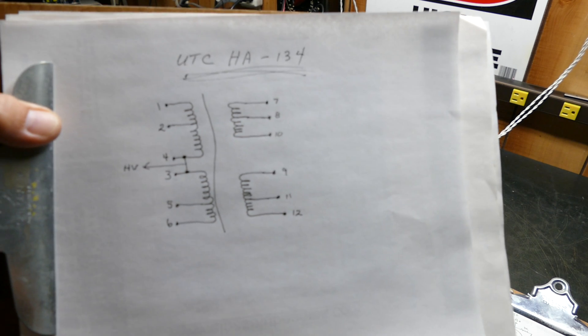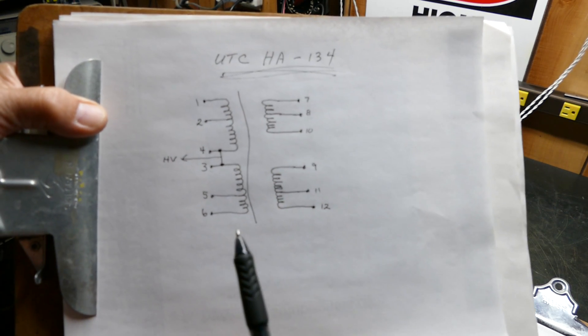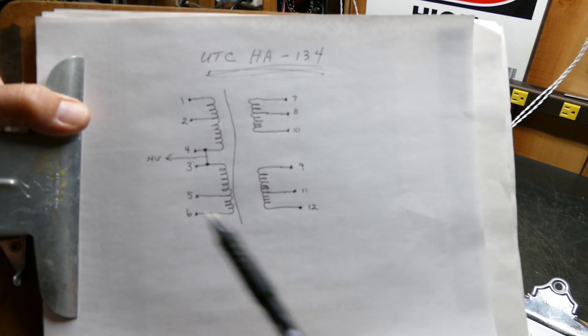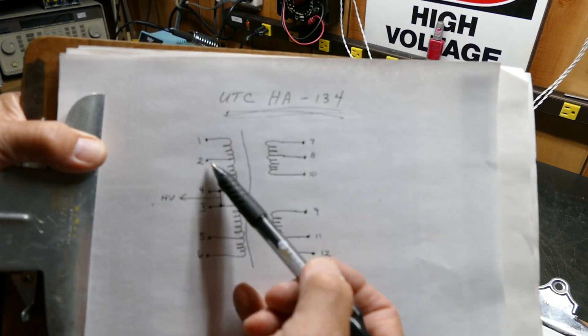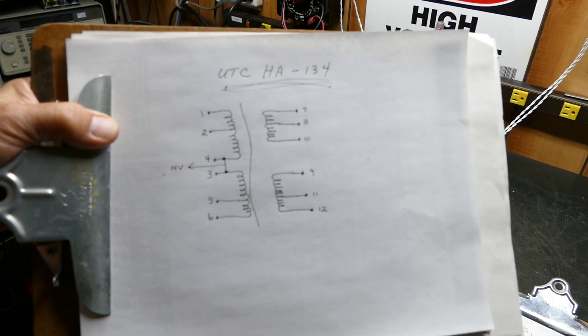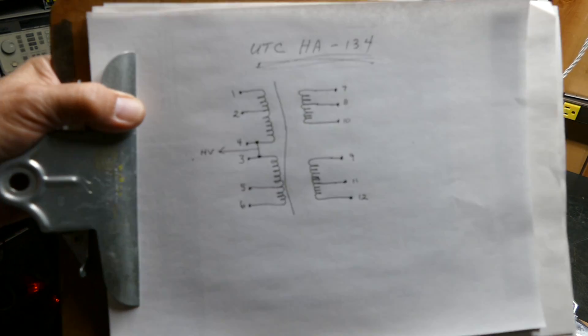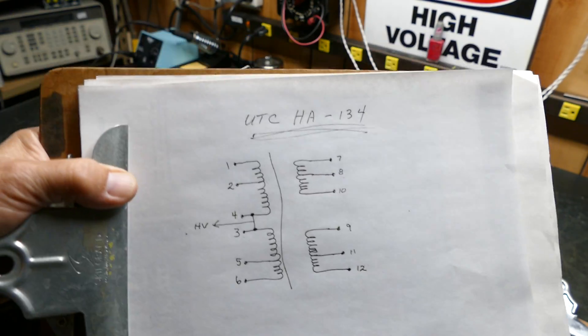I'm going to show you. I'm going to strap it their way. We'll do the voltage readings. We'll take those ratios. We'll square it. We'll put 50 over here, and you'll see that you get 5k and 10k over here. Let me show you how that's done. If you've watched any of my videos before on transformers, you know what I'm about to do.